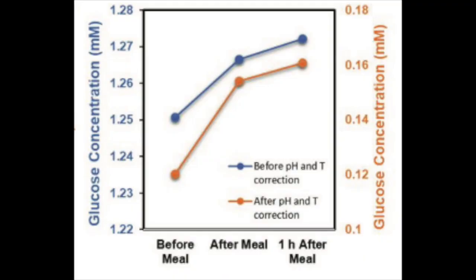Second, everybody's sweat is different. We sweat different amounts of liquid, and our sweat has different levels of salt and sodium, which may impact the interpretation of the glucose measurement. And thirdly, differences in temperature and temperature changes, whether it's skin temperature or ambient temperature, can also have an impact on the glucose measurement, or at least the interpretation of it.